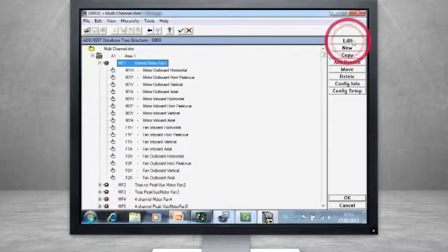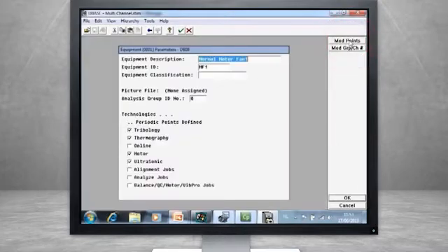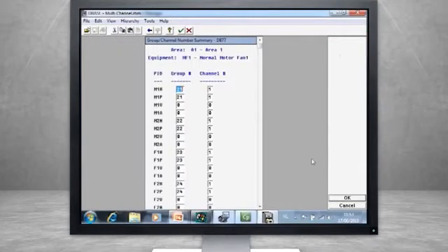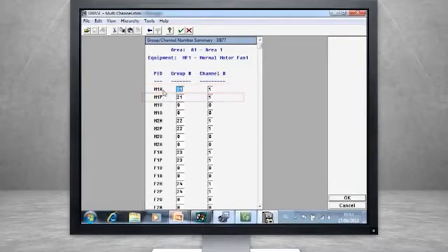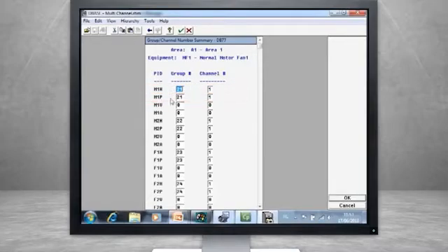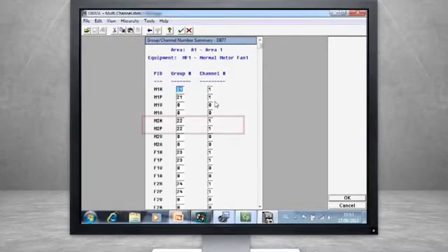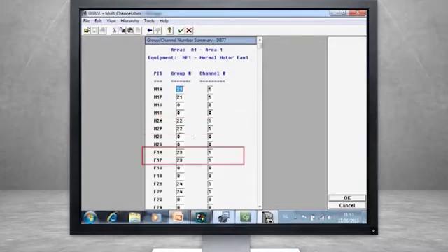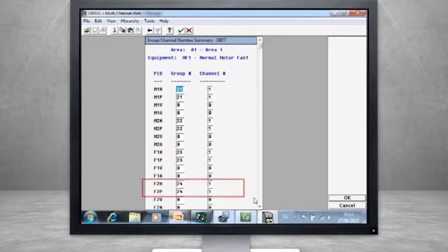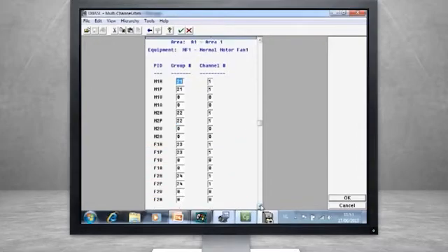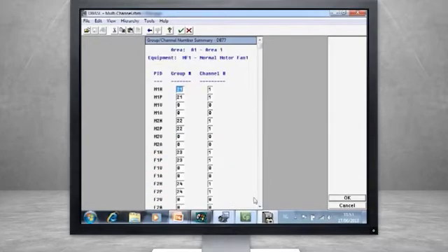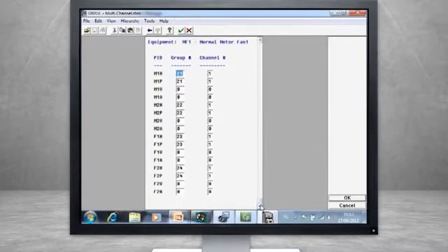Select Edit from the right navigation and then select Modify Group Channels. Here you see a screen showing Motor Outboard Horizontal and Motor Outboard Peak View. The first two measurements shown are in the same group and same channel. This means their measurements will come from a single accelerometer. In this example, the Peak View measurement is always taken simultaneously with the Motor Outboard Horizontal measurement.